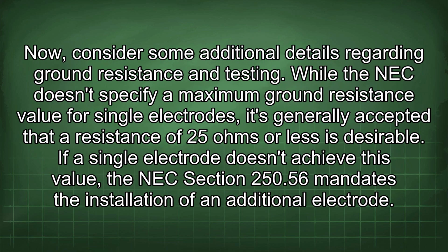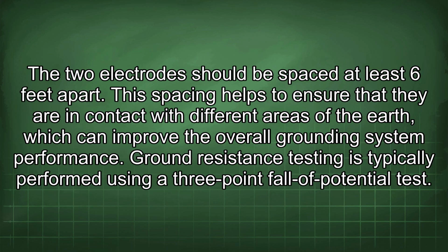Now, consider some additional details regarding ground resistance and testing. While the NEC doesn't specify a maximum ground resistance value for single electrodes, it's generally accepted that a resistance of 25 ohms or less is desirable. If a single electrode doesn't achieve this value, the NEC section 250.56 mandates the installation of an additional electrode. The two electrodes should be spaced at least 6 feet apart. This spacing helps to ensure that they are in contact with different areas of the earth, which can improve the overall grounding system performance.